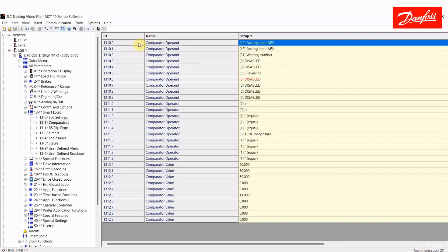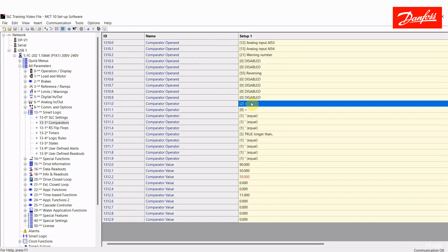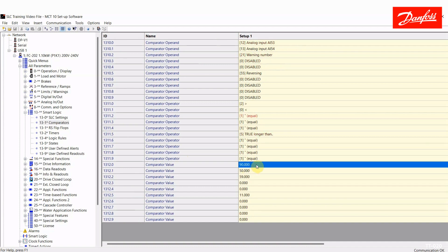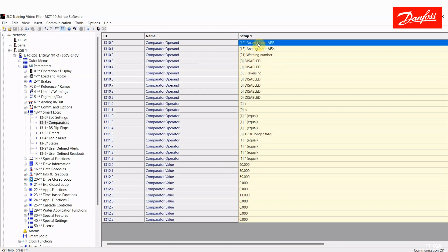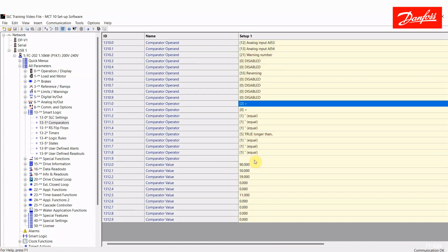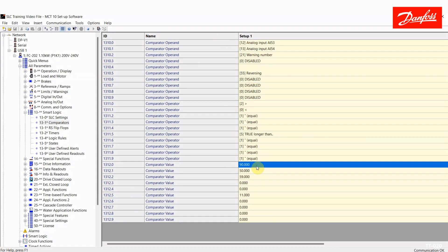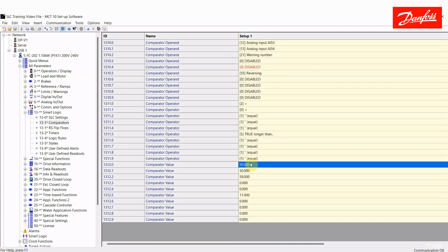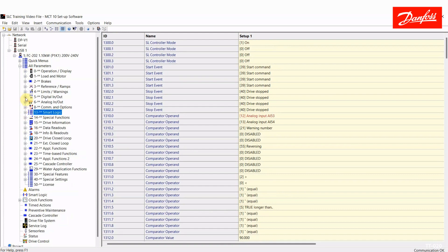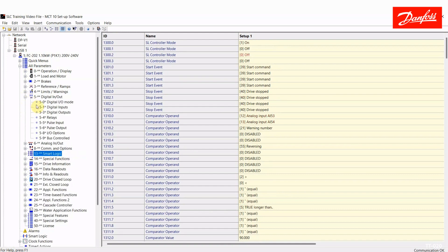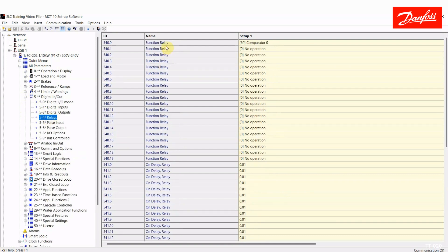Comparator 0 here has been set to say that analog input 53 is greater than 90. Now, it takes some experimentation to understand what all the values are or what type of number you should enter here. In this particular event, analog 53 is greater than 90% of the maximum scaled value of analog 53, which happens to be 10 volts. So, comparator 0 would be true when analog input 53 is greater than 9 volts or 90% of 10 volts. So, that comparator has actually been attached to relay 1 here.